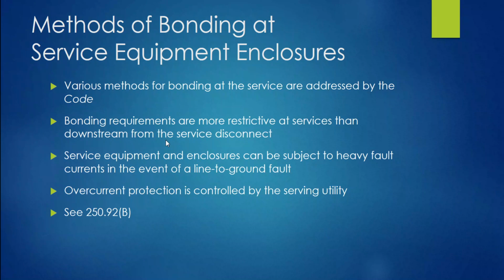All right, the method of bonding at the service. Various methods of bonding at the service are addressed by the code. We've talked about quite a few of them here. The bonding requirements are more restrictive at services than they are downstream. That is so very true. So you have to do all these things and make sure everything stays an assured type of bonding situation on the line side of the service equipment, or the service disconnecting means. But on the load side, you can use standard lock nuts.